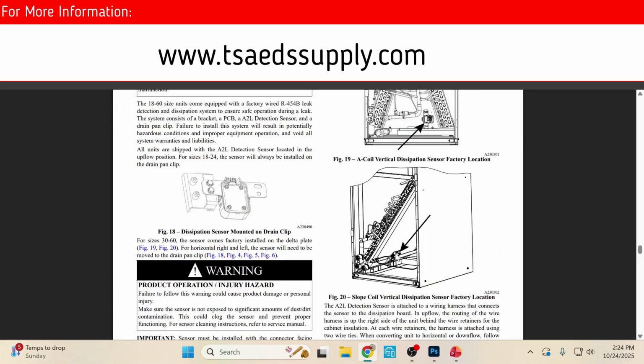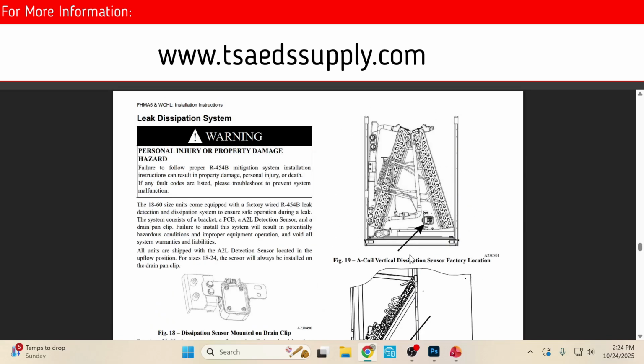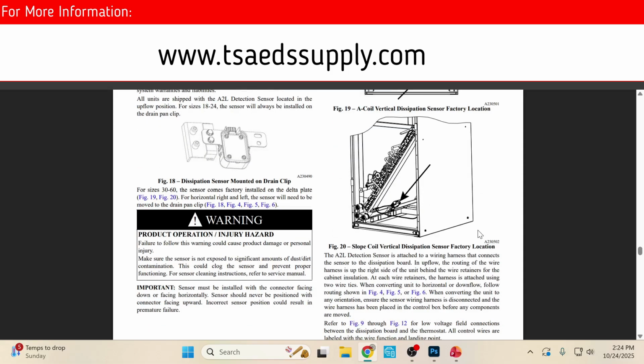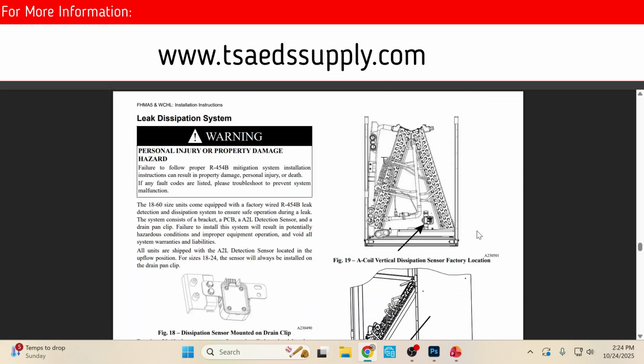On this, you're going to see the sensor here is at the bottom. The Freon is heavier than air, so the lowest point in the unit is roughly where they're going to have this sensor, which is here in the vertical position. If you go to move it in horizontal, you may have to move it over to here. Or if you're moving it horizontal right, it'll probably stay where it's at.